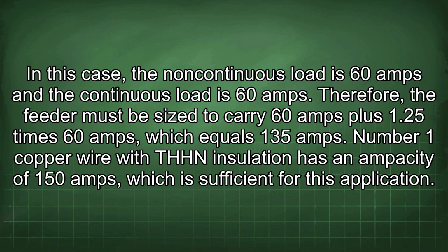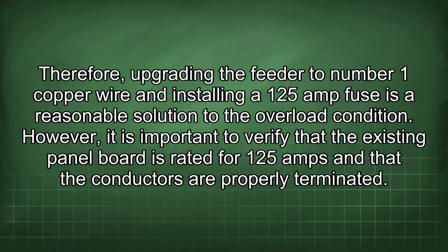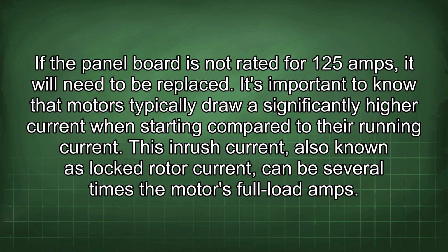Number 1 copper wire with THHN insulation has an ampacity of 150 amps, which is sufficient for this application. Therefore, upgrading the feeder to number 1 copper wire and installing a 125 amp fuse is a reasonable solution to the overload condition. However, it is important to verify that the existing panel board is rated for 125 amps and that the conductors are properly terminated. If the panel board is not rated for 125 amps, it will need to be replaced.